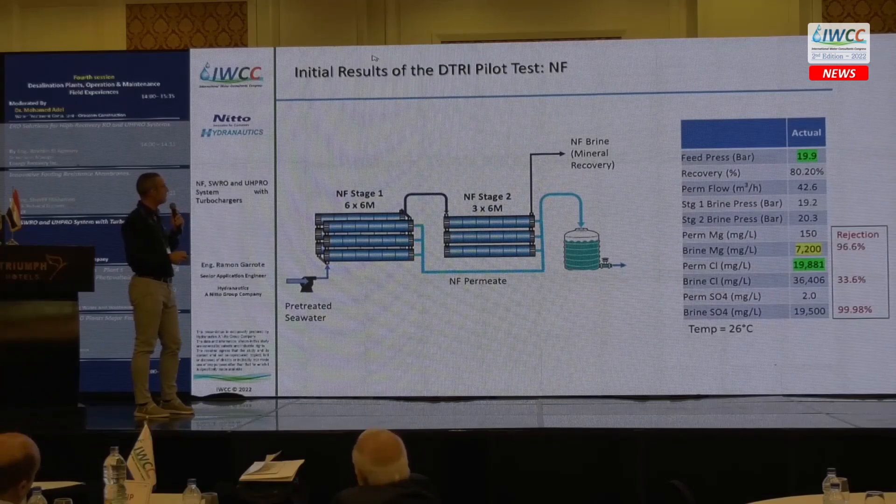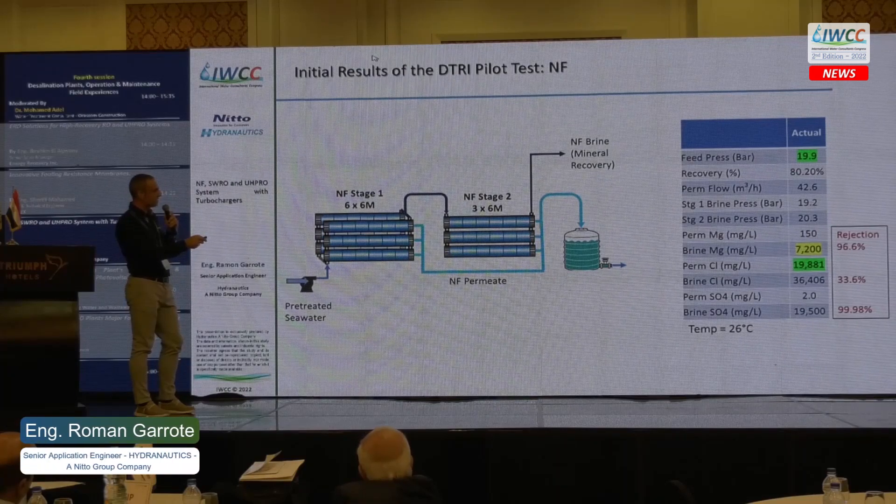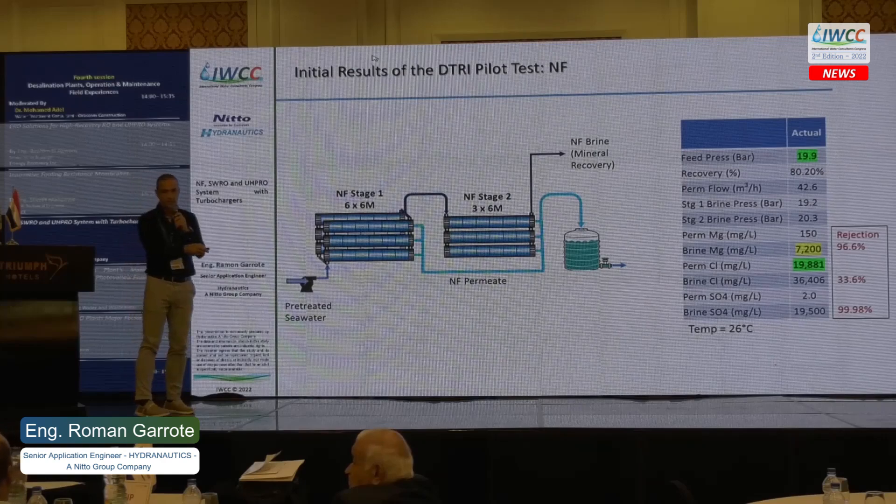This is the initial data from the NF system. We are running at about 20 bar pressure and 80% recovery. Looking at ion rejection, we have 96.6% for magnesium, 33.6% for chlorides, and 99.98% for sulfate — sulfate rejection is very high for this membrane.